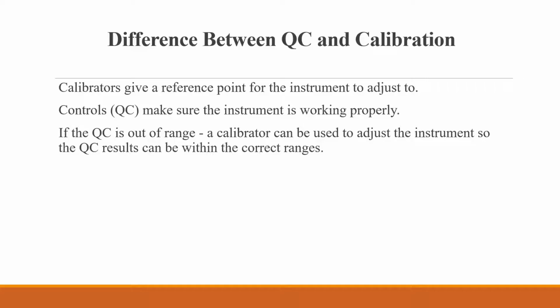If we produce packed red cells, we have to do quality control at least once a month. If we produce platelets, plasma, or cryoprecipitate, we have to do quality control on them. If the quality control is out of range, we need to use a calibrator to adjust the instrument so that the quality control could be brought back within the correct ranges.